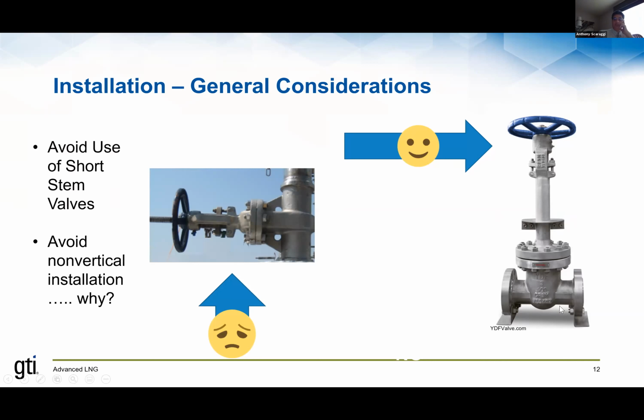So picture this, and why do you want to do this, right? Picture this, you've got LNG at minus 260 degrees in this valve, and then LNG rises in this valve handle, right? Inside this valve handle, the LNG begins to vaporize and forms a vapor pocket. And that vapor pocket actually seals the valve stem in the valve. That's the design of a cryogenic valve, the basic way a cryogenic valve works.